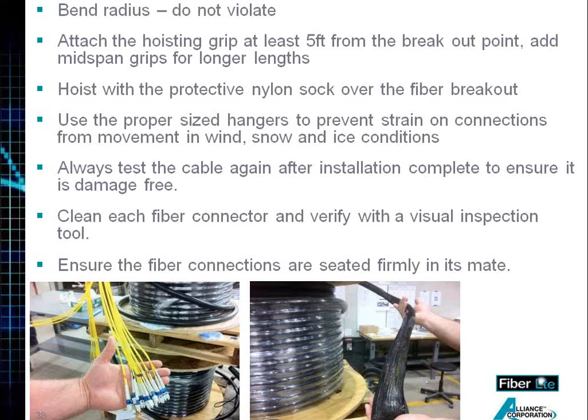Always test and inspect the cables once the installation is complete. It is important to keep copies of all tests on file. This is your way to prove that when the cable was installed, it tested as per the manufacturer's recommendations.